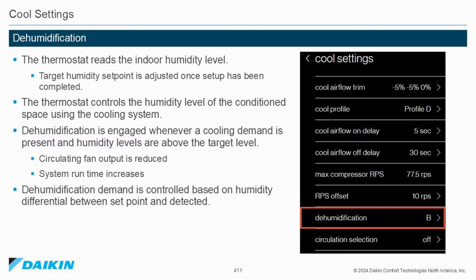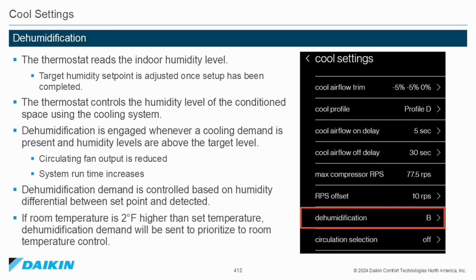Dehumidification demand is controlled based on the humidity differential between the set point and the detected humidity. If the room temperature is 2 degrees Fahrenheit higher than the set temperature, dehumidification demand will be sent to prioritize room temperature control.